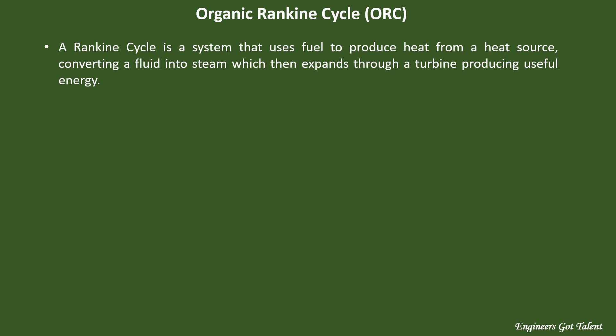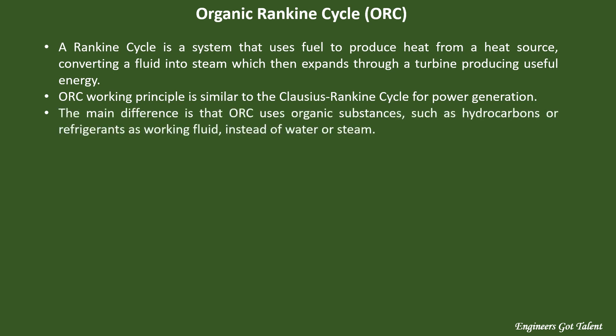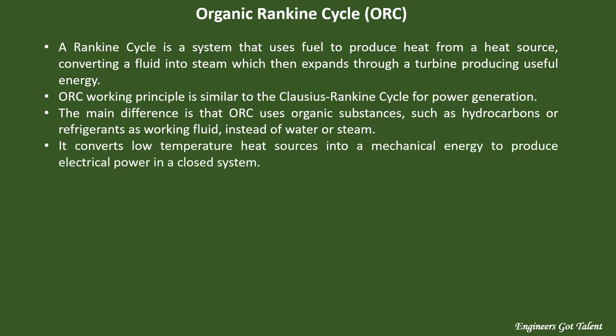Organic Rankine Cycle, or ORC. A Rankine Cycle is a system that uses fuel to produce heat from a heat source, converting a fluid into steam, which then expands through a turbine producing useful energy. ORC working principle is similar to the Clausius Rankine Cycle for power generation. The main difference is that ORC uses organic substances, such as hydrocarbons or refrigerants, as working fluid, instead of water or steam. It converts low-temperature heat sources into mechanical energy to produce electrical power in a closed system.